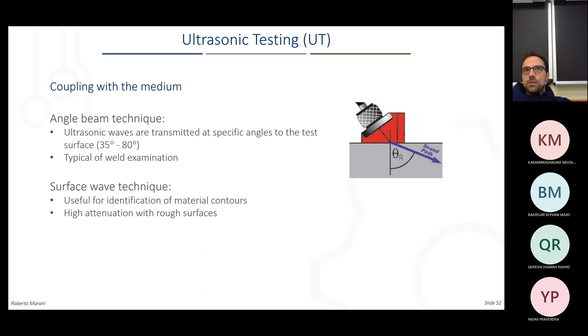As I said, once you define a setup, you should take care of the transducers and the setup that you can create, whether it is a transmission or reflection setup, and so on. The couplant that you need to add to your system also depends on what you are investigating. For example, you cannot use water if your material has some problems with water. This is of course another point of the setup, the pulser receivers.